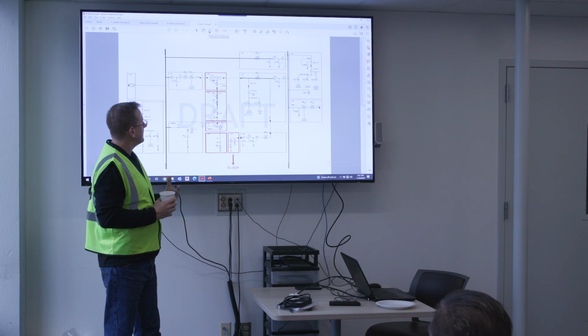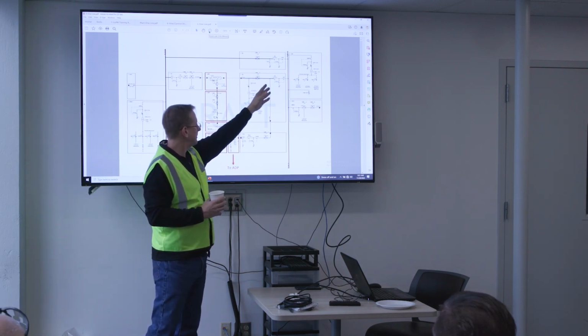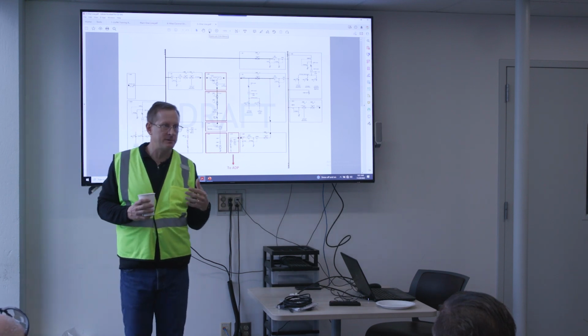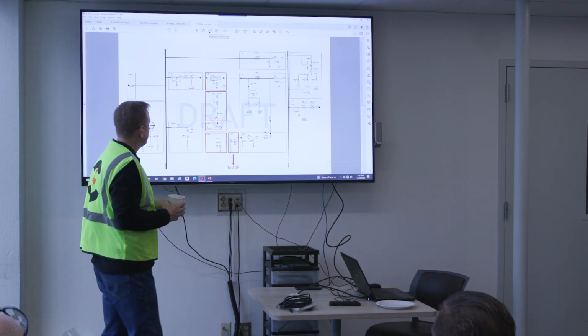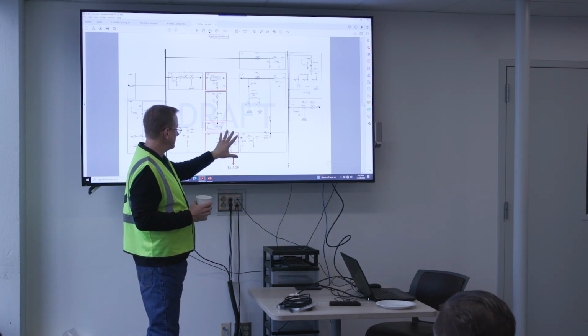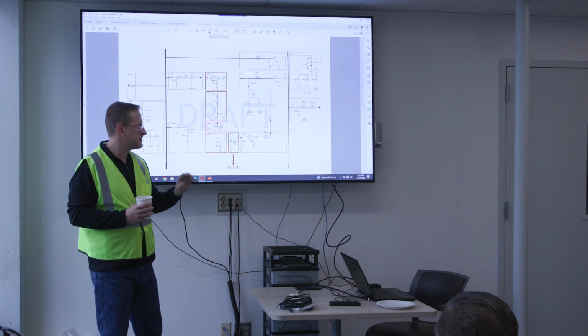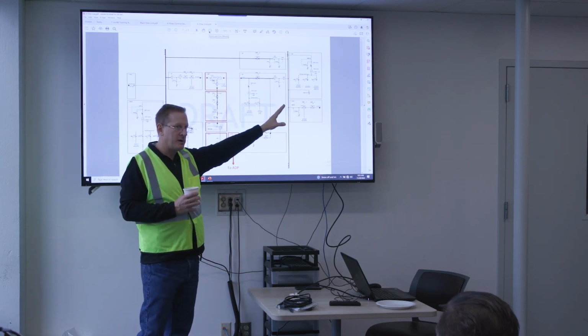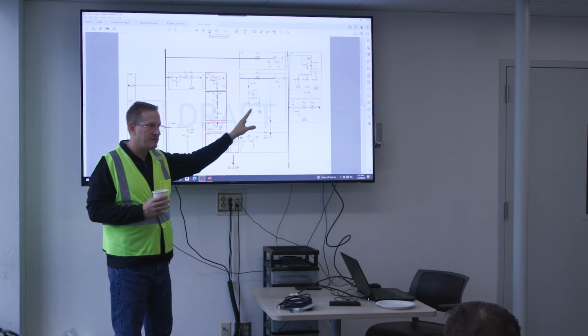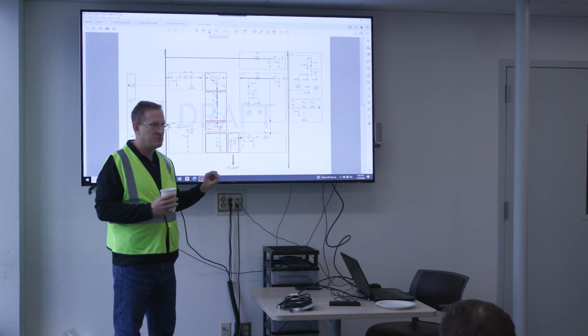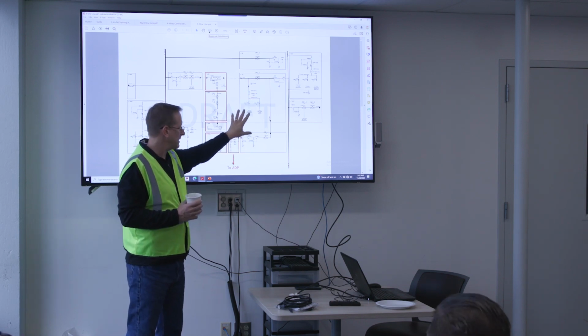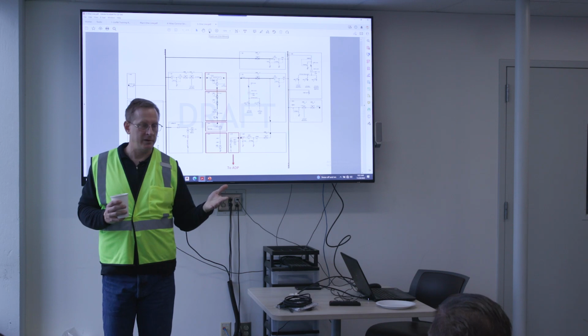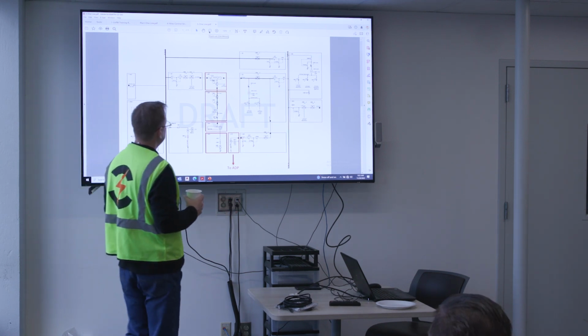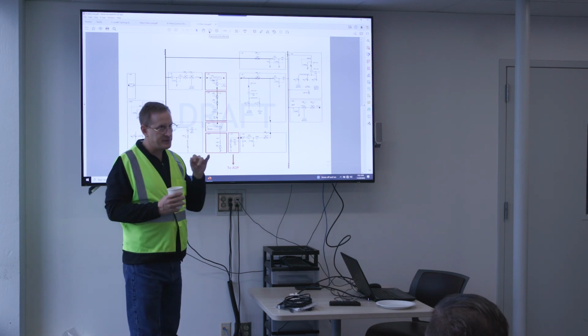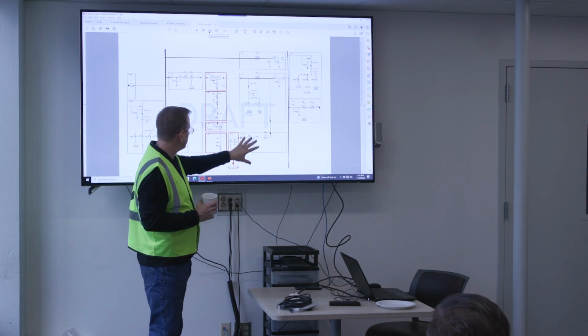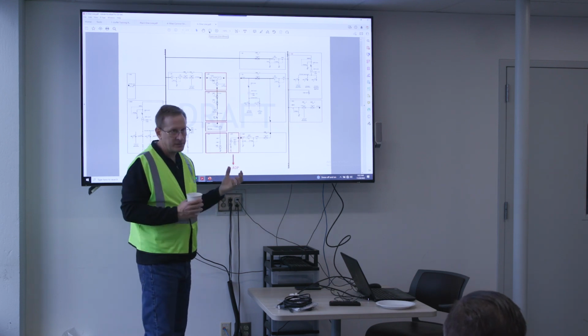And of course, we want that to be sourced from the critical output, so that that source never goes away. So that becomes a critical source that is fed by the output of our system. That is not included in your rating of the system. In other words, the rating of the system, what you can put on the system at your output, is 1955. This does not detract from that. So we've already accounted for these loads that we need to run our system. It doesn't take away from your load rating on the output. GTP stands for Generator Transformer Panel. So again, that's just the transformer that feeds the ADP for the low voltage loads.